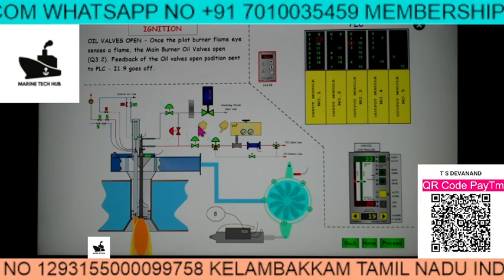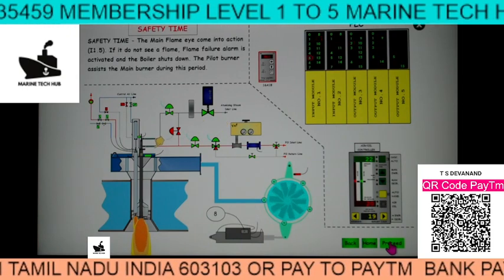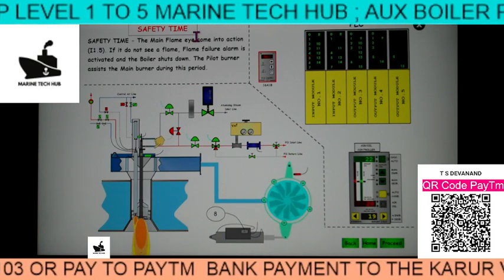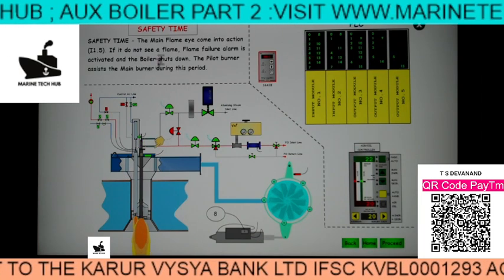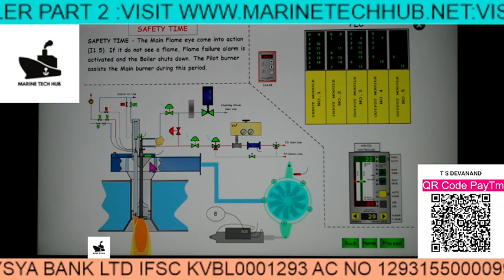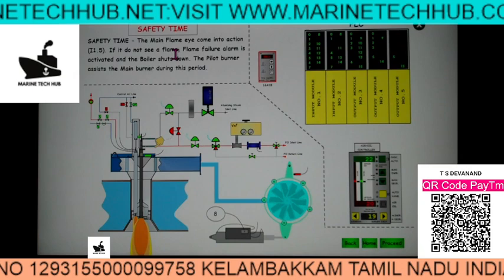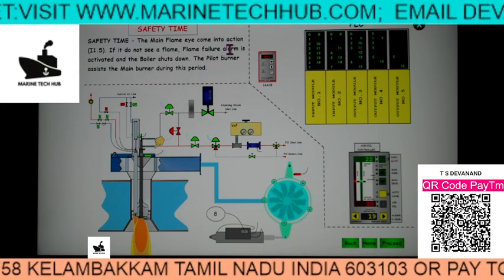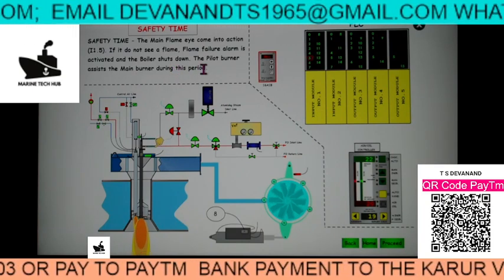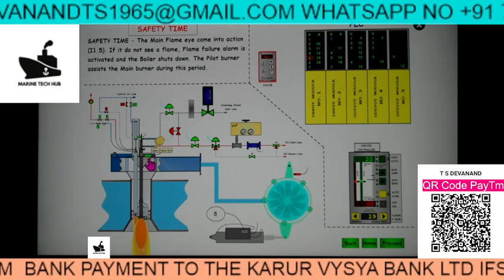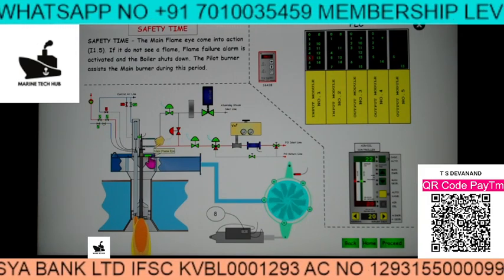Once you stop, the steam purge valve will open and push any remaining oil through. After this, there is the safety time. During safety time the system checks whether the main burner is working correctly, and later the pilot burner will be switched off. The main flame eye — I1.5 — comes into action. If the flame sensor is not sensing the flame, the flame failure alarm will be activated and the boiler will shut down. The pilot burner assists the main burner during this period. If the sensor is faulty, there will also be a shutdown even if the flame is present.